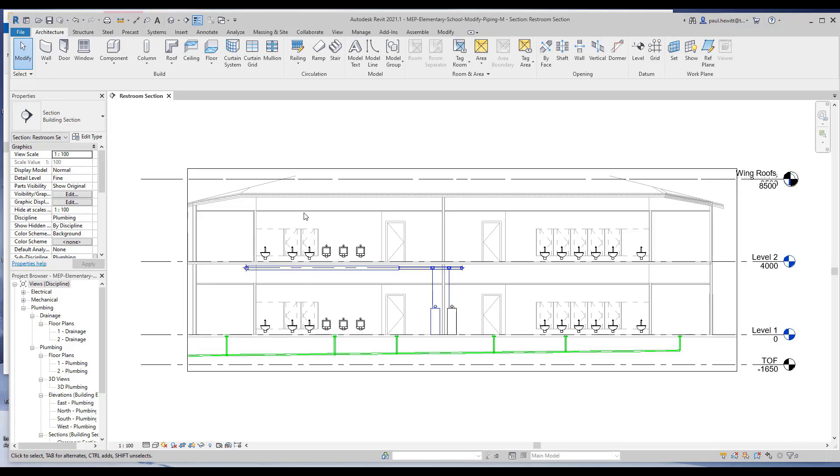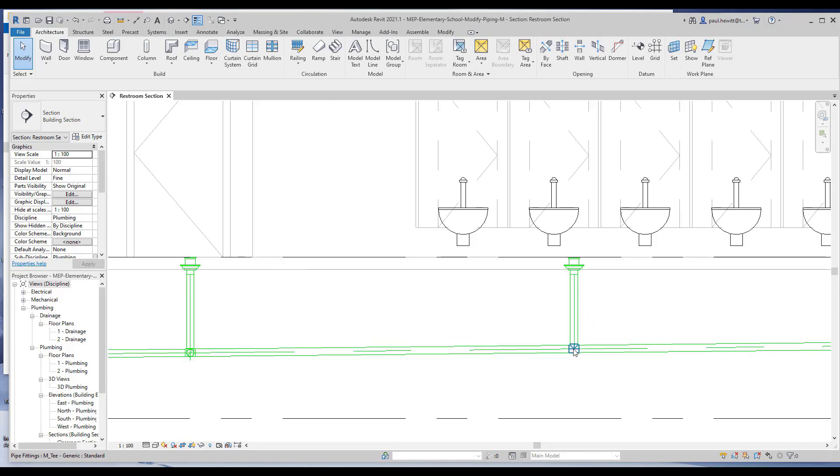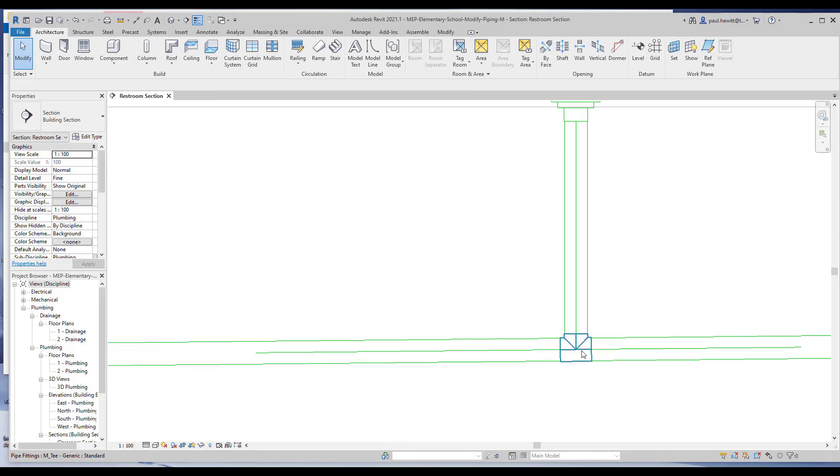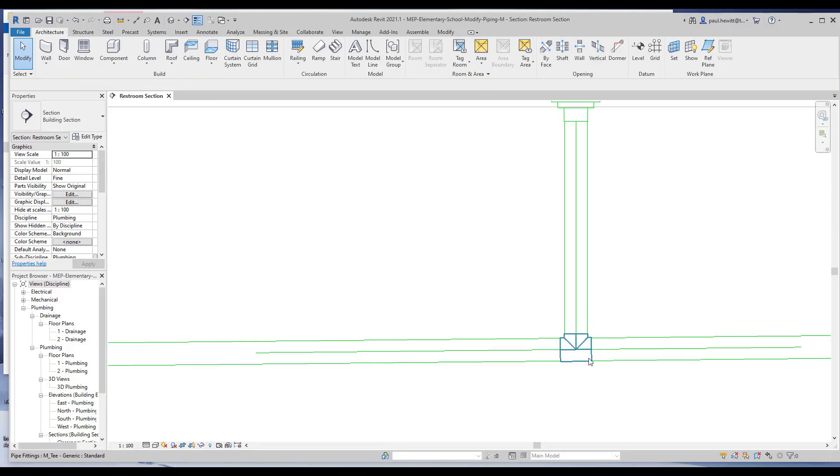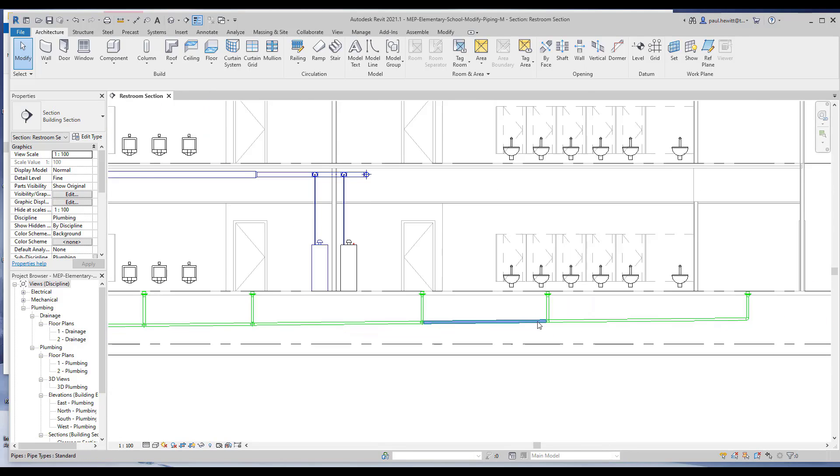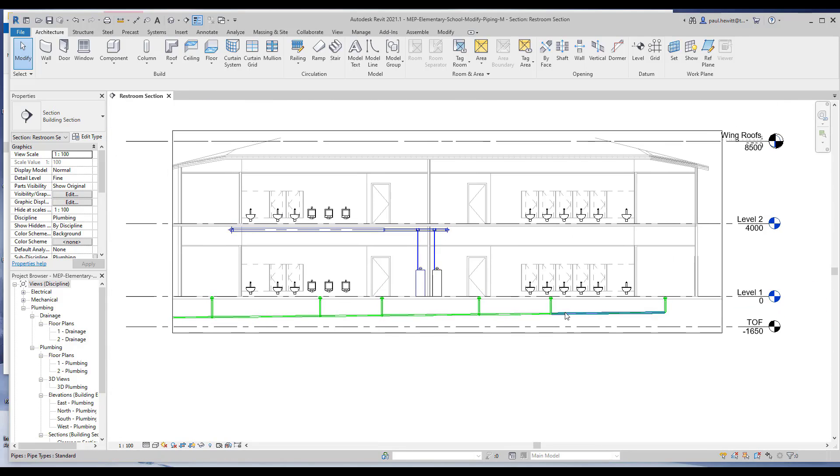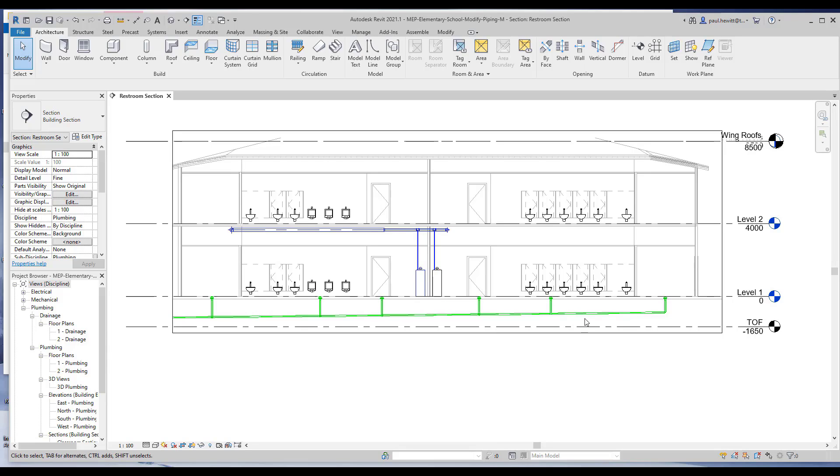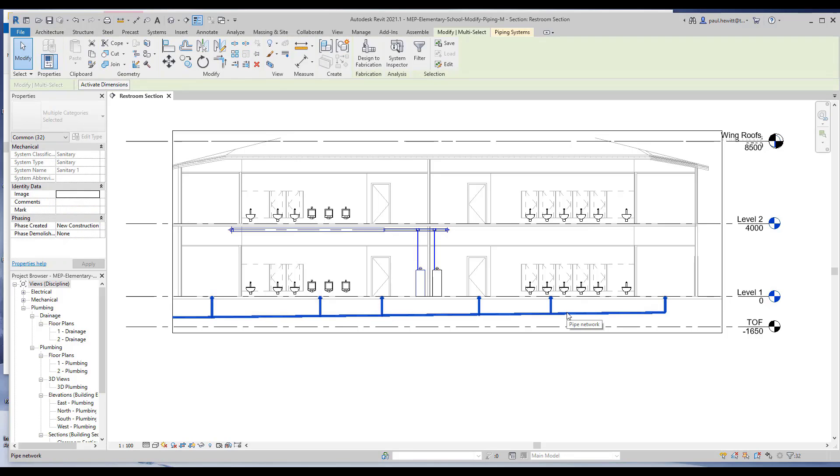So the first thing we'll look at is the sanitary piping we already have, and we're using a standard piping, so the connectors aren't correct at this point. Now rather than going around and changing these connectors, we're going to select the pipe run and change that pipe run. If I hover over one part of the piping and hit the tab key a number of times, it'll highlight the whole pipe. Tab a couple of times, and then pick to select.